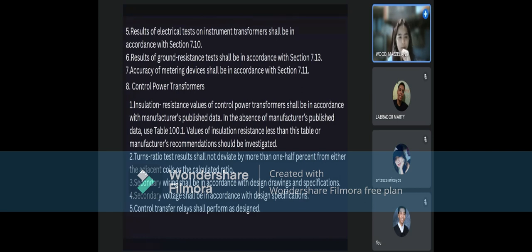Number 8, control power transformers, and under number 8 is insulation resistance. Values of control power transformer shall be in accordance with the manufacturer's published data. Just like the previous ones, they should follow the manufacturer's published data, and if not, they need to use Table 100.1, which we will see later. And then number 2, turns ratio test results shall not deviate more than 0.5% from either the adjacent coils or the calculated ratio. So it should not deviate by more than 0.5% from the adjacent coils or the calculated ratio in the turns ratio test.